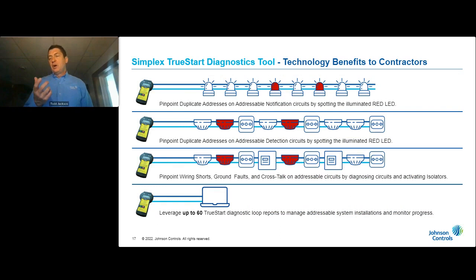A lot of times you don't know what the condition of the field wiring is until the fire alarm panel shows up. So as we talked about earlier, best demonstrated practices are test your branch circuits before the system gets there. We have a tool, and I'm sure there's other manufacturers out there that have it, but ask for it.